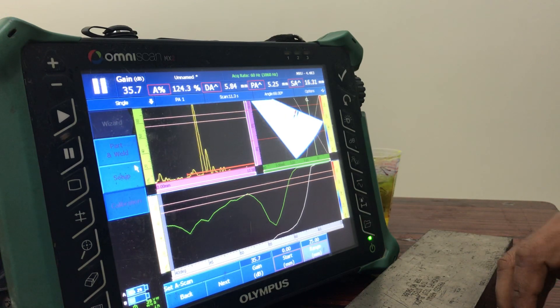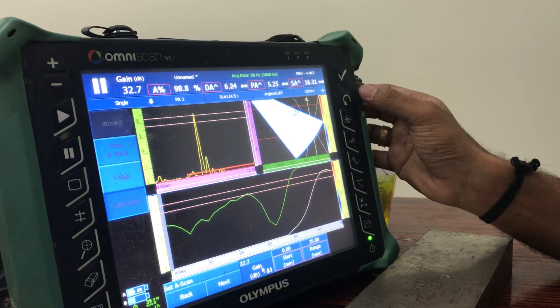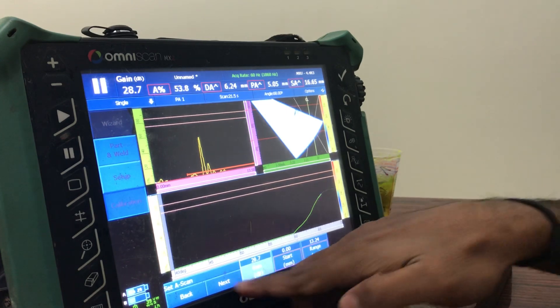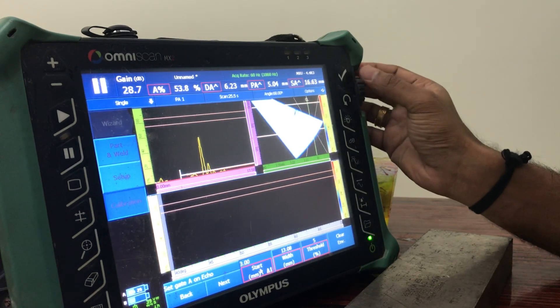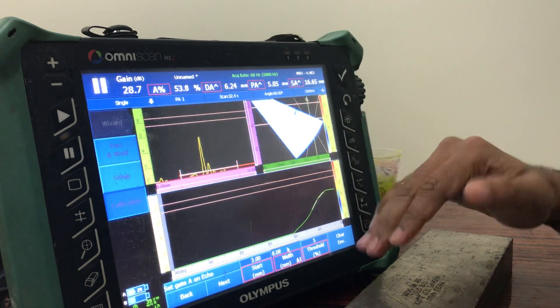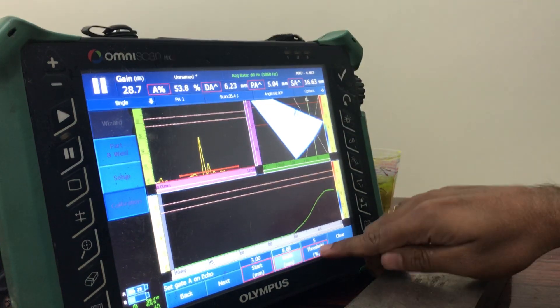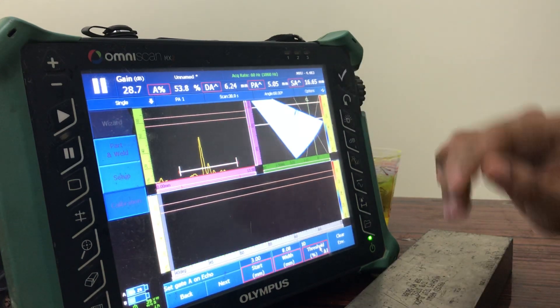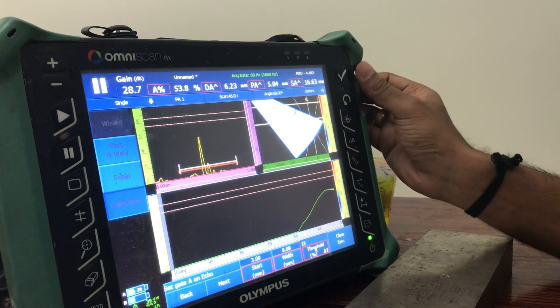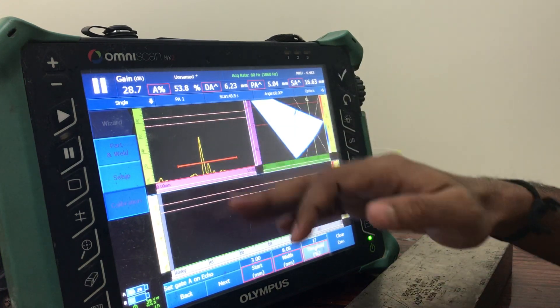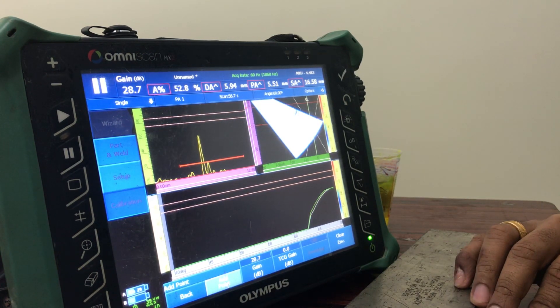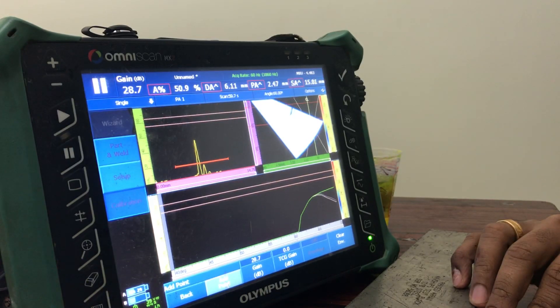The echo is saturated, so reduce the gain (dB). Reduce it and start catching the echo. The threshold is set at 10. Ignore the echo from the tip — fix the gate position carefully, otherwise it will disturb the main echo and cause problems.